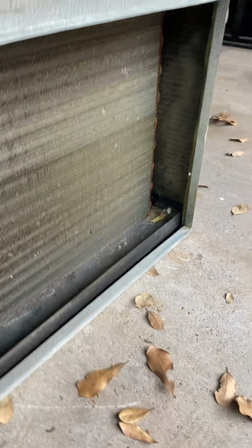Now, you could also put what's called a watchdog or a float valve on your secondary drain pan, which you always see is underneath the unit, and that actually will float the valve or the ball up and kill your unit completely, which obviously then you'll know there's a problem, but it will stop flooding your house if it starts to get over that drain pan line. It kills the unit. Called a float valve or a watchdog.